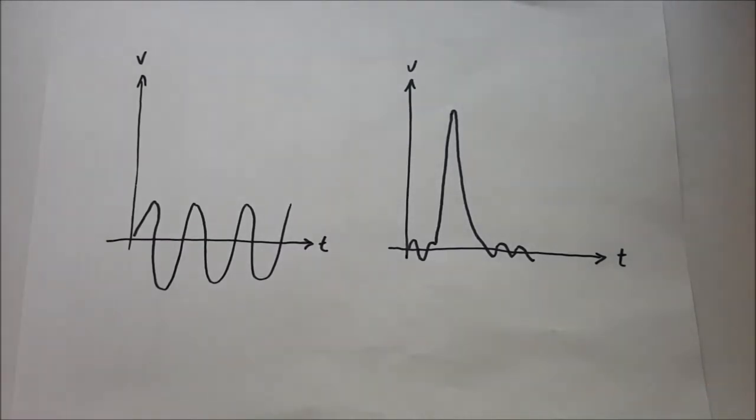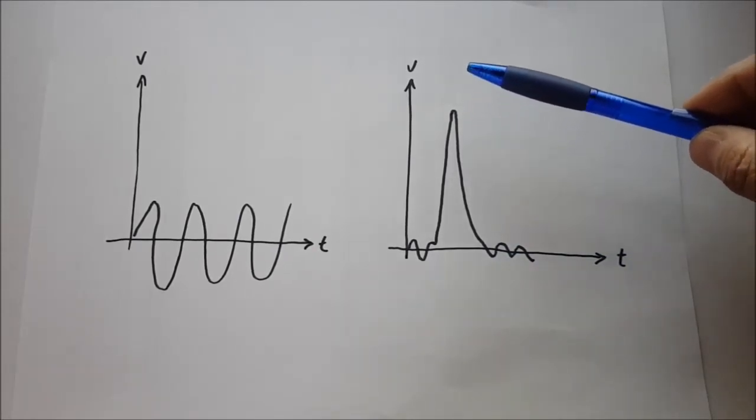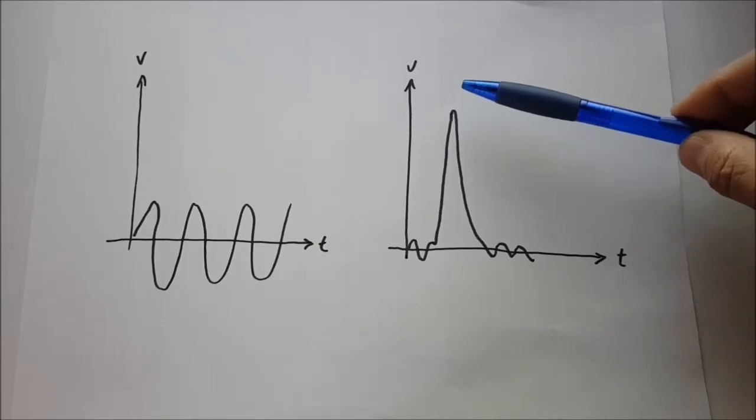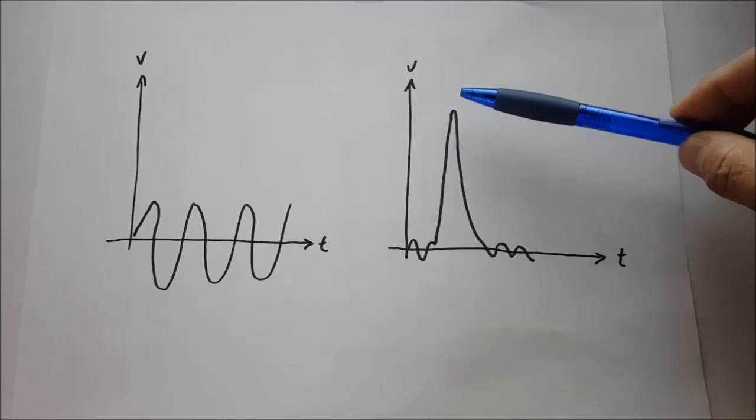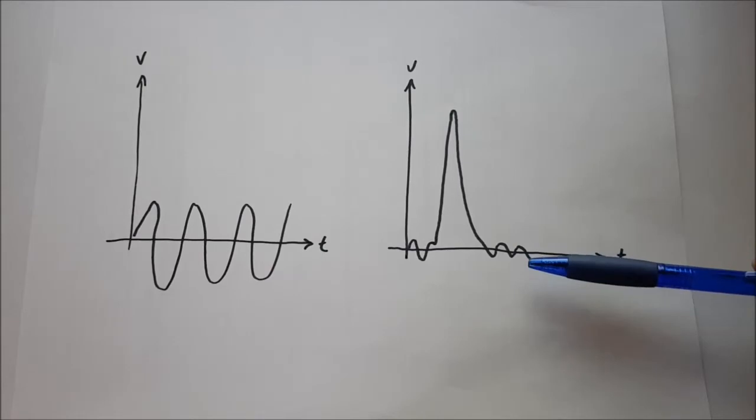This is a very dangerous situation with an IT system when you are isolated from somewhere but you are getting energy induced into your system. The voltage can only rise until the moment it has to breach insulation somewhere. The energy can escape to the ground, go back to earth. That will reduce the surge again, but it will always be together with a probable destruction of electrical equipment, which you of course don't want to have.